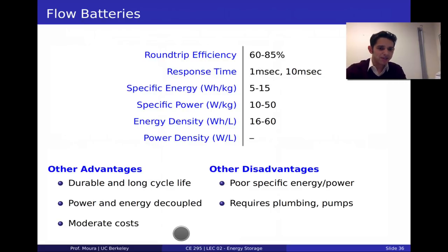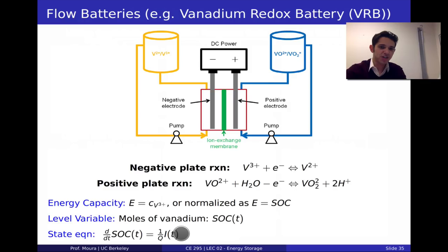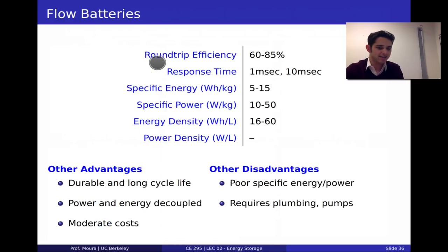What's great about them is that they're quite durable. They have long cycle life. It's basically just pumping fluids around. What's also very cool about it is the power and energy are decoupled. Namely, if I install one of these things, the size of my pumps gives the power density. And then completely independent of that, I can design the size of my tank, and that's the energy density. So we can decouple those. That's unique. With other battery technologies, we can't decouple the power and energy capacity.